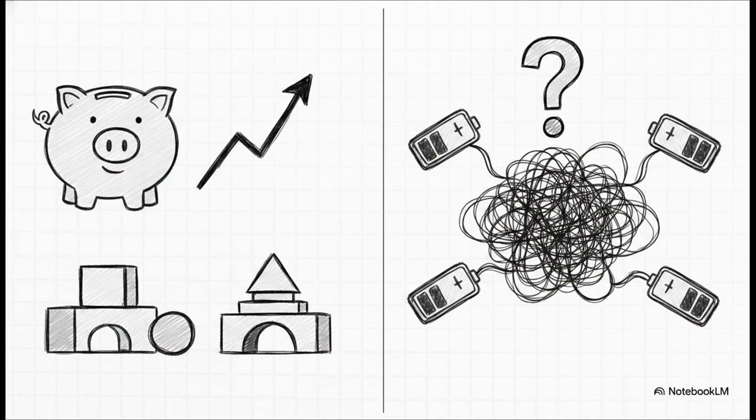The advantages of the 3 out of 4 system are absolutely compelling. It is highly economical, highly scalable, and uses smaller individual equipment. It's a total financial win for massive power demands. But the disadvantages? You now have 4 complex machines to physically synchronize instead of 3, which means a much more complex control circuit. Plus, as we just mentioned, there's that slightly higher normal load rate of 75%.